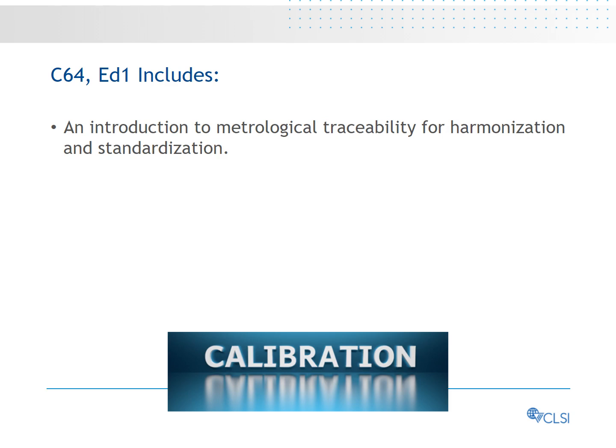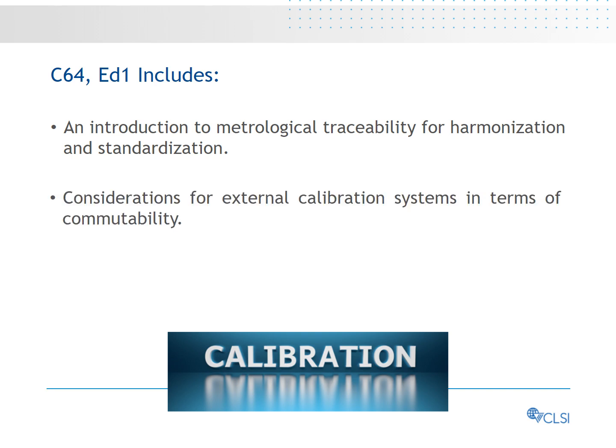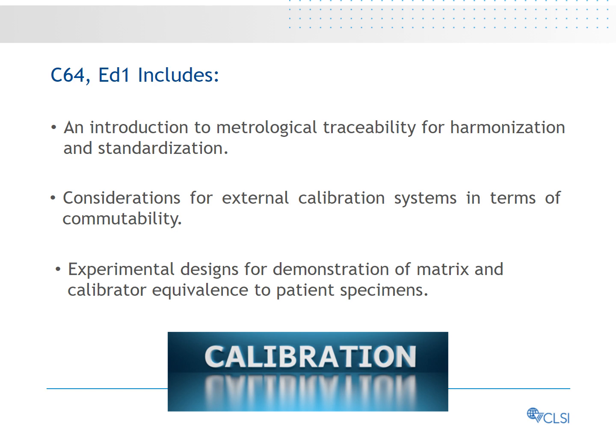Calibration is required for all quantitative protein and peptide measurement procedures used in a clinical setting. This process provides the fundamental link between a measurand and metrology. Calibration is central to harmonization and standardization and should be considered during test design. The response factor is the relationship between the detector response and the number of analyte molecules initially present in a defined sample volume, i.e., analyte concentration. Calibration can be external or internal. Calibration errors arise when the response factor function represented by the calibrator system is non-equivalent in the test specimen, i.e., native matrix. The ideal calibrator matrix is identical to the specimen matrix used in testing. Choosing the right calibrator is critical to ensuring the accuracy and trueness of a measurement procedure.